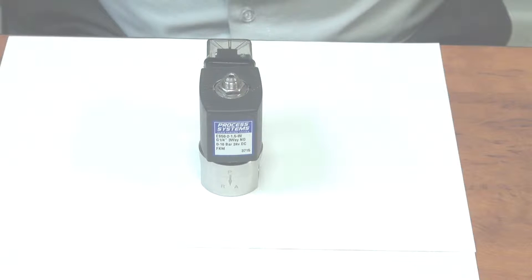The ES58 solenoid valve is a three-way normally open valve suitable for applications where you want to pass a signal through when there's no power on it. It's a normally open function. When it's energized, it cuts that signal off.